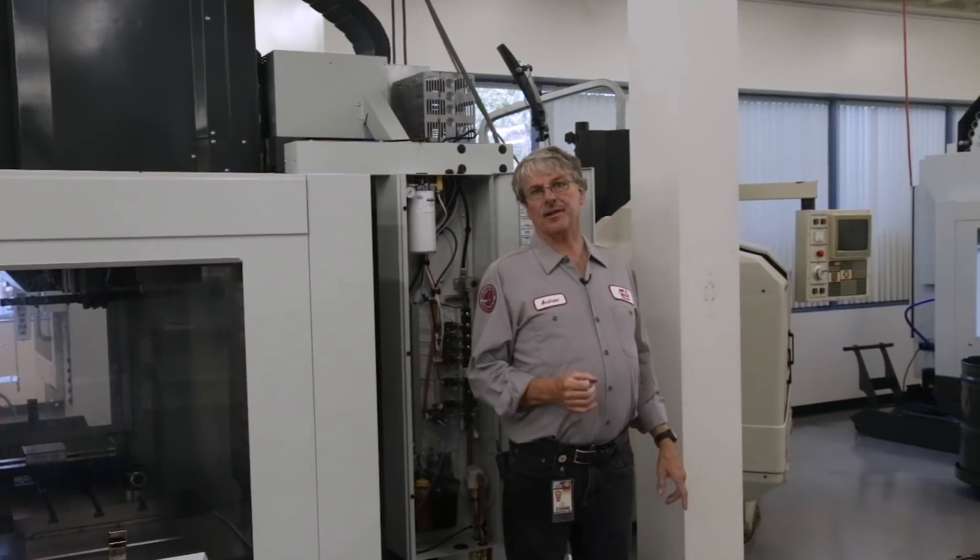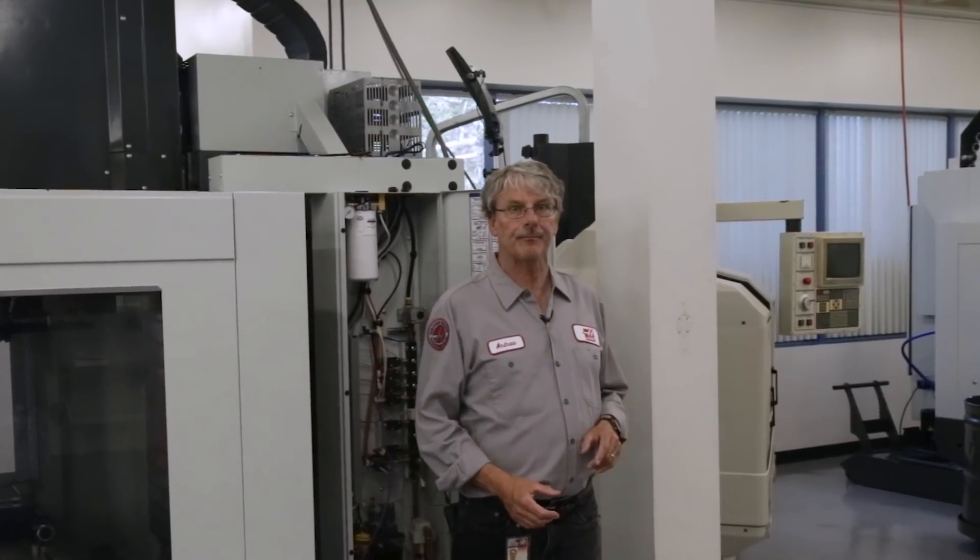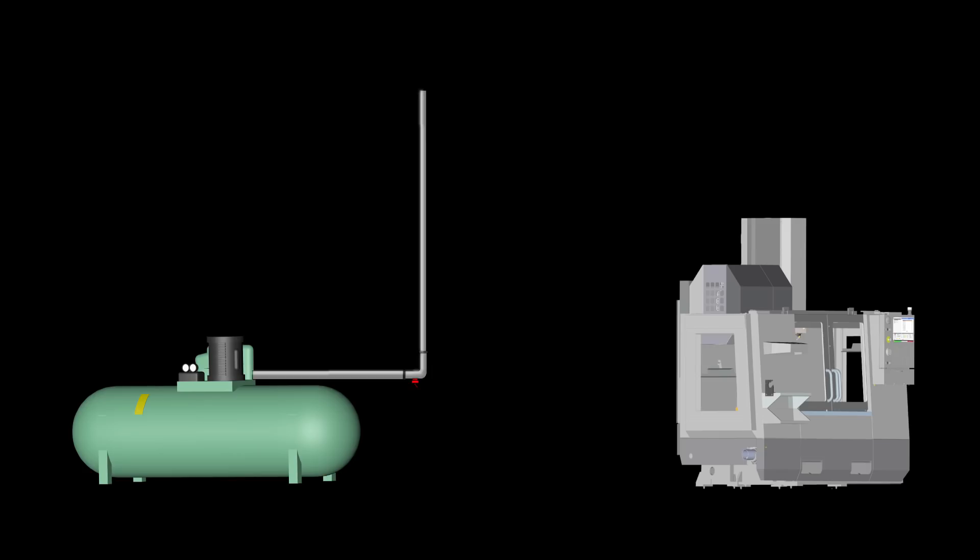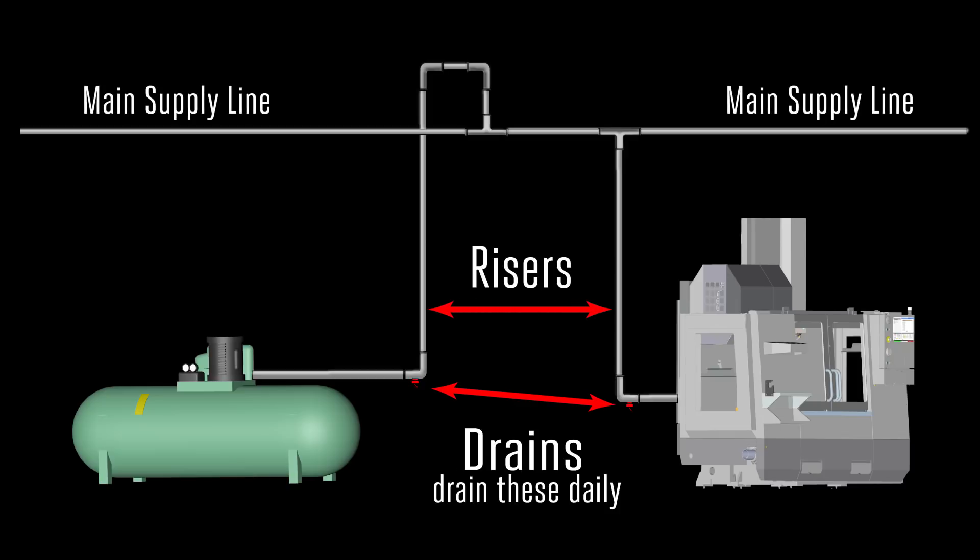Of course, an air dryer is the best way to combat the problem of water in your air, but those aren't cheap. Luckily, there's another way to deal with this issue. When you plumb air to your machines, always use vertical risers with drains at the bottom and attach machine drops from the top of your main air supply line. Any moisture in the system will tend to fall away from the path of the compressed air.